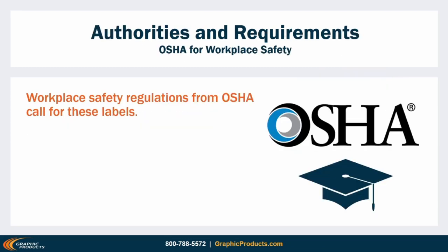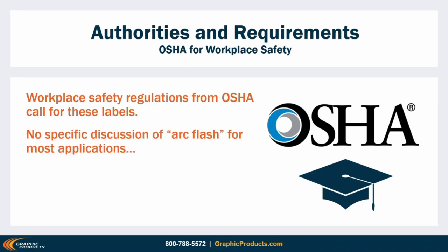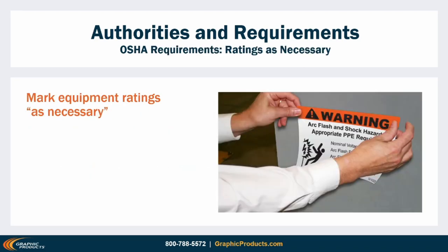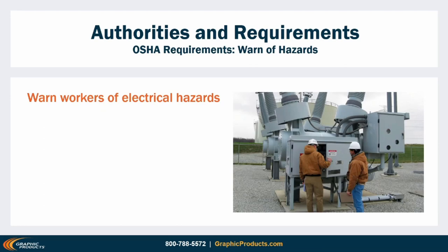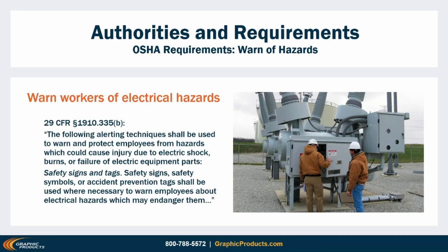Arc flash hazard labels are also required by workplace safety laws. Here in the United States, OSHA's regulations only specifically mention arc flash at the utilities level, but several of their regulations for general workplaces also apply. OSHA requires electrical equipment in the workplace to be marked with voltage, current, wattage, or other ratings as necessary. This starts with manufacturer labels, but employers are responsible to provide the information needed for the use and maintenance of the equipment.